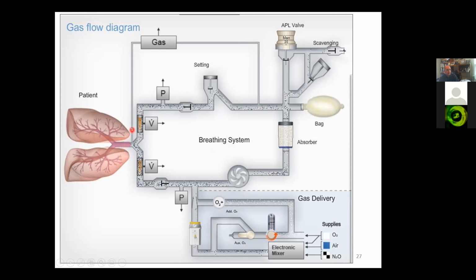The very first line here is a thin tube that samples the gas at the patient's airway, essentially at the new artificial mouth here, to do chemical analysis of it. This is the analyzer. The line here is indicating the signal path from the analyzer to the alarm system and the displaying computer displays. And then that gas is returned to the breathing circle. The gas gets from wall oxygen and air and nitrous oxide, an anesthetic gas, through a blender system into the pumping and regulating system through a fail-safe valve to the patient.